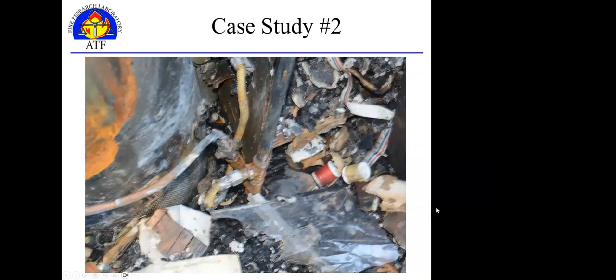Not the best photo, but what you can see here is a gas line coming in, coming down the main line. You've got this yellow flexible gas appliance connector that comes to the water heater. And then here's another valve and a 1/2-inch copper line that goes off behind the water heater.